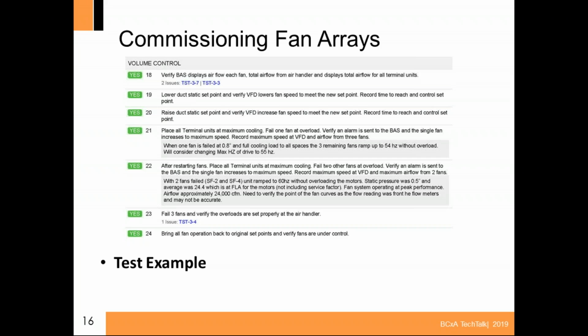And sure enough, I got right on the edge of it, 24.4 for the 2 motors running, and was not operating in the service factor. I put down there, not including service factor. Never operate a motor in the service factor range when you set it up. It's just not good practice. So at that point it was operating at peak performance of 24,000 CFM because these fans are way out at the end of the curves. And I said, okay, I'm going to go back and look at the drive, and it passed the drive test.